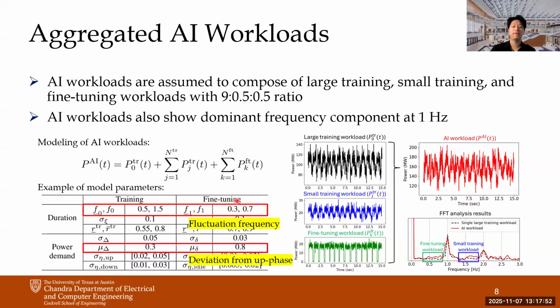In the case of the fine-tuning workload, they have a lower fluctuation frequency, between 0.3 and 0.7 Hz. Here, the mu parameter represents the deviation from the high power dimension to the lower power dimension. The fine-tuning workload has larger deviations between the high and low power dimensions. Based on these mathematical models, we can synthetically generate the AI workload shown in the right figure.